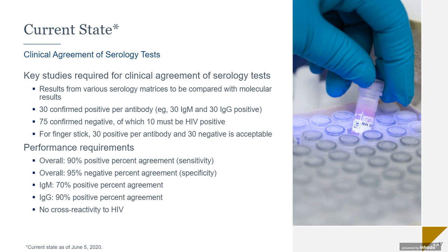So we talked about the clinical agreement a little bit. Clinical agreement studies and performance expectations for serology tests are described in this slide. Whether a manufacturer is planning their own prospective study or taking advantage of the umbrella pathway for independent testing, the assay will require a clinical agreement study of at least 30 positives and 75 negative samples. The current information from FDA is that comparison must be performed to an EUA-authorized molecular test, preferably collected at the same time. We hope this changes down the road and that companies are able to demonstrate studies against other EUA-approved serology tests, but that's just not the way things are today.